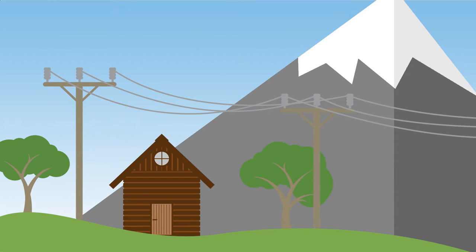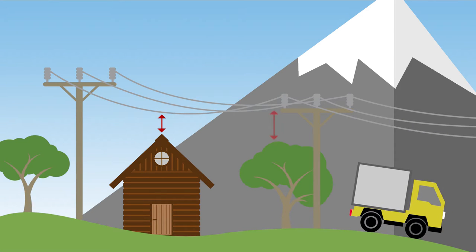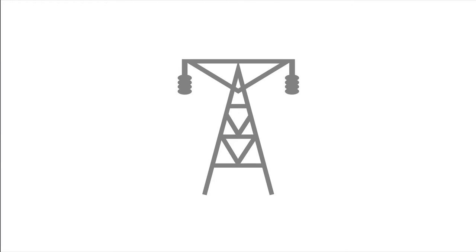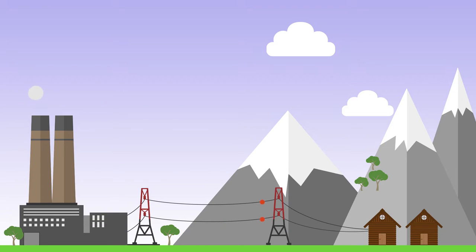Reliability may be in terms of electrical clearance, whereby we will ensure that the voltage-dependent clearance requirements are met for every object along the line route. Reliability may also be in terms of structural capacity, where the design limitations of all structures and cables are respected. Utilization refers to the amount of electrical load transfer that can be performed through the line, circuit or network.